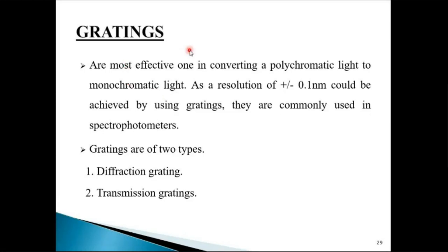Gratings can be compared to a computer CD disk. Basically, what it has is a polished surface, and on that polished surface you have successive grooves. Because of these grooves, which are very small — micro size — it causes diffraction of light. It is the most effective one in converting polychromatic light to monochromatic light. A resolution of plus or minus 0.1 nanometer can be achieved by using gratings. They are commonly used in spectrophotometers.